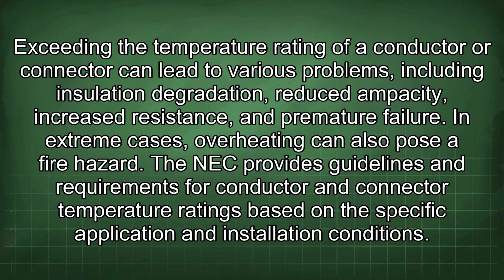Exceeding the temperature rating of a conductor or connector can lead to various problems, including insulation degradation, reduced ampacity, increased resistance, and premature failure. In extreme cases, overheating can also pose a fire hazard.